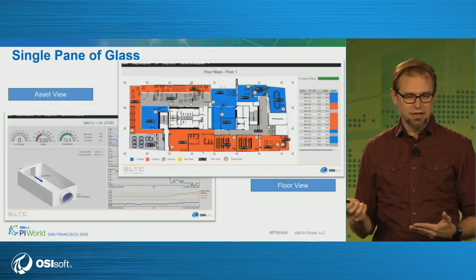We'll talk about the heating and cooling that was happening at the same time, say on vacations like July 4th, which is a holiday in North America, or well, in the US portion of North America, and how we identified that. We talked about some of the view glass and how that doesn't always work the way that's intended, or it maybe dims too early or too late, and that's been troubleshot both with the control systems, the BACnet controllers, and then also those IoT devices.